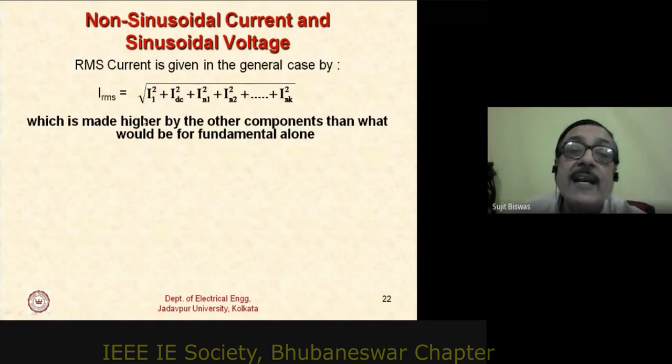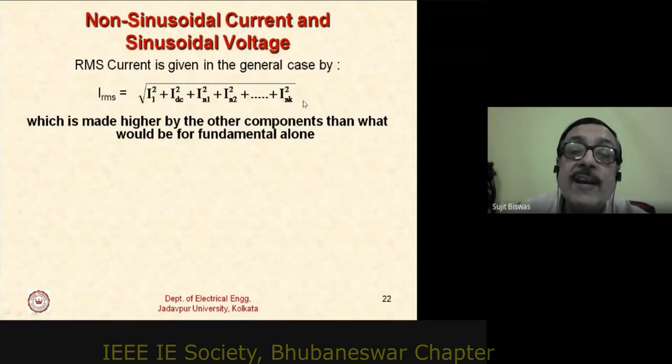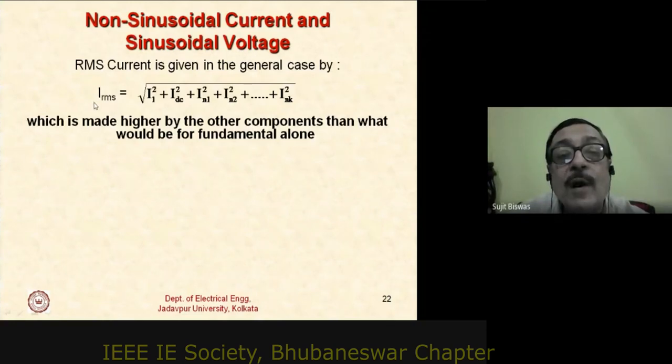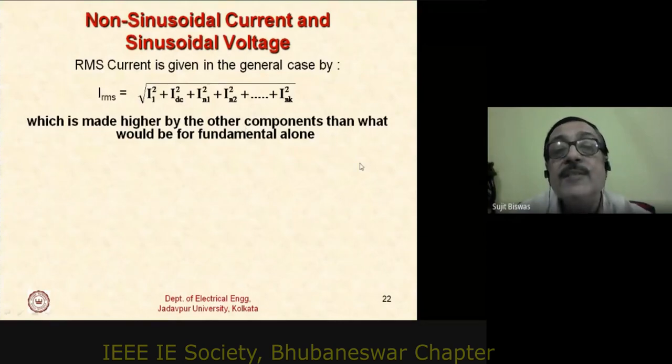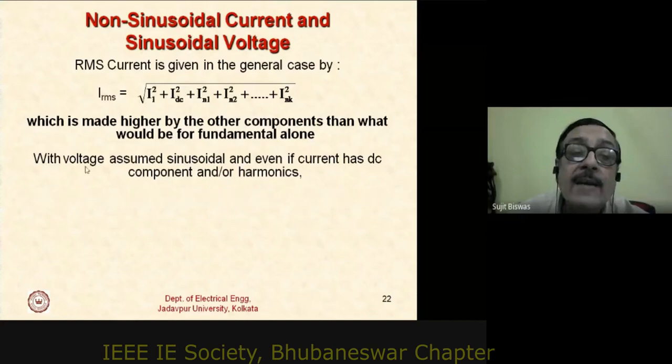In the general case, RMS current is expressed as: I_rms = √(I₁² + I_dc² + I_a1² + I_a2² + ...). The RMS magnitude is therefore much higher than for the fundamental alone. Since the voltage is assumed sinusoidal, average power is consumed only by the fundamental current component. Substituting into the power factor expression, the numerator contains only V_rms·I₁·cos(θ₁), while the denominator contains V_rms·I_rms — which is larger due to harmonics — so power factor is reduced.